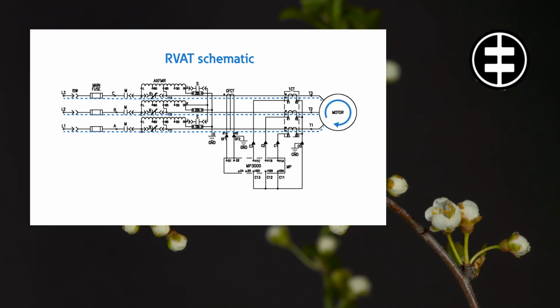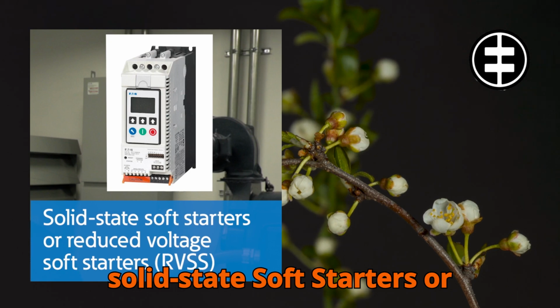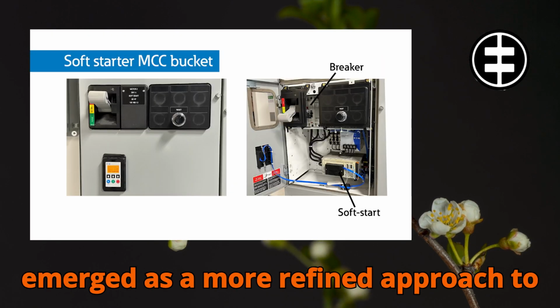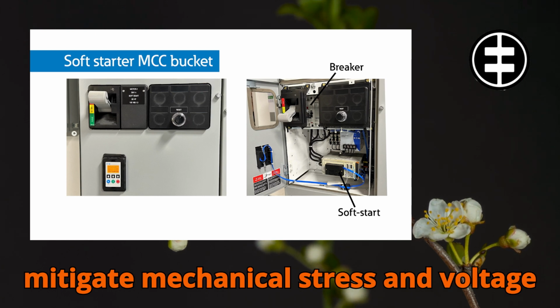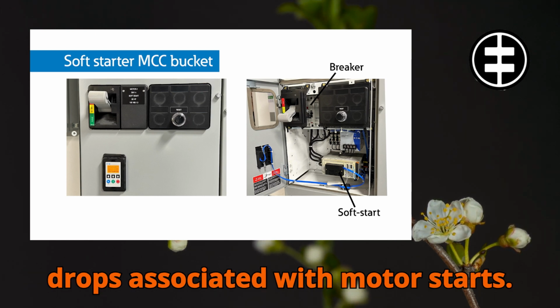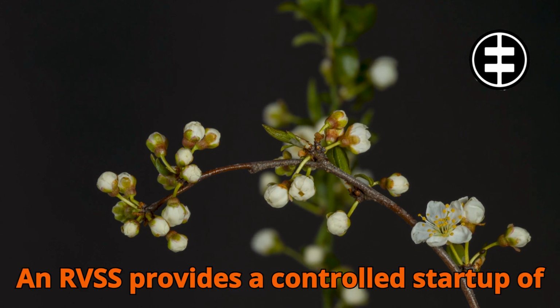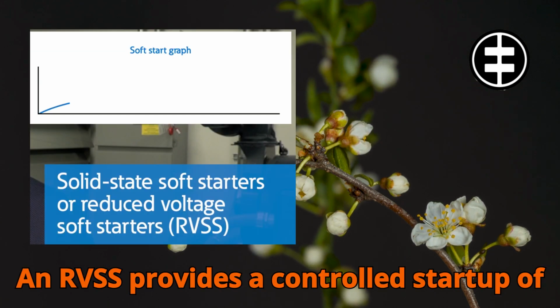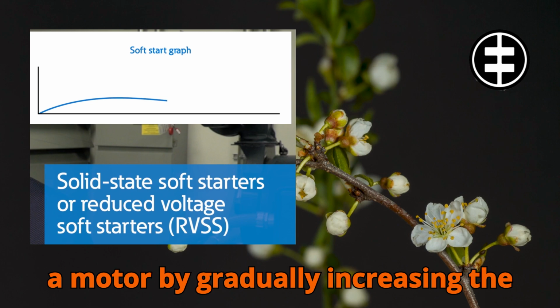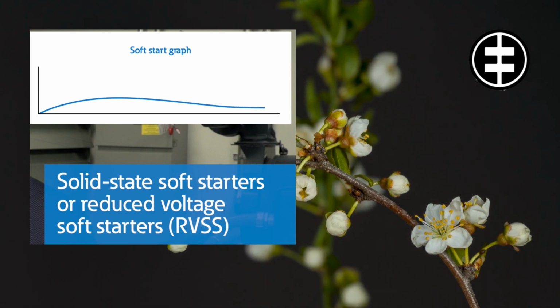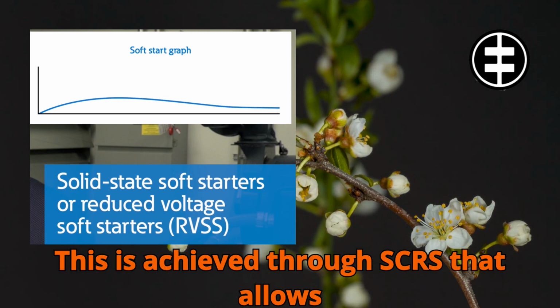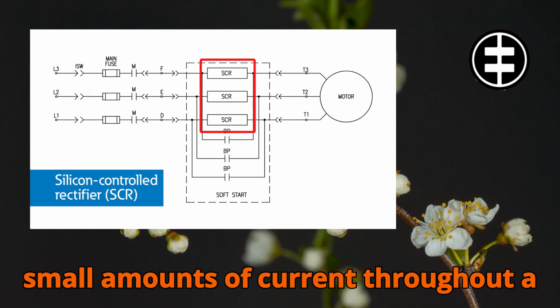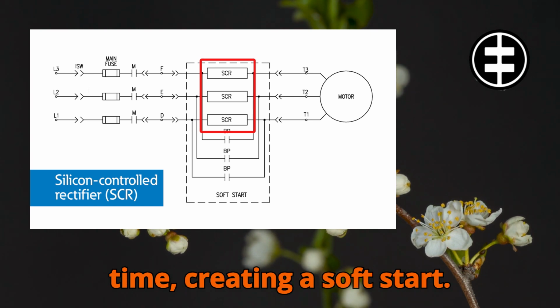Once the motor ramps to full speed, the motor is connected to full line voltage through the opening and closing of contactors. Solid-state soft starters, or RVSS, emerged as a more refined approach to mitigate mechanical stress and voltage drops associated with motor starts. An RVSS provides a controlled startup of a motor by gradually increasing the voltage output. This is achieved through SCRs that allow small amounts of current through over time, creating a soft start.